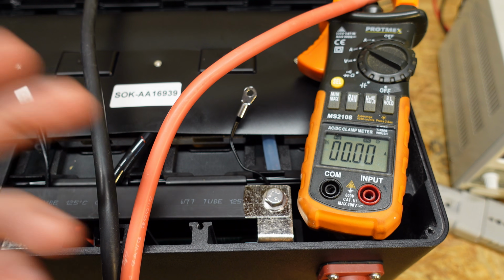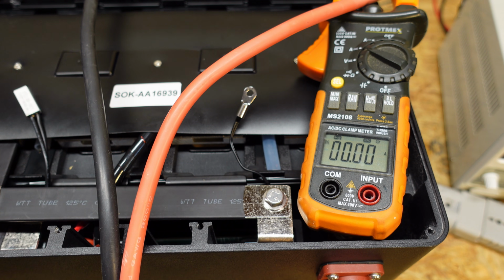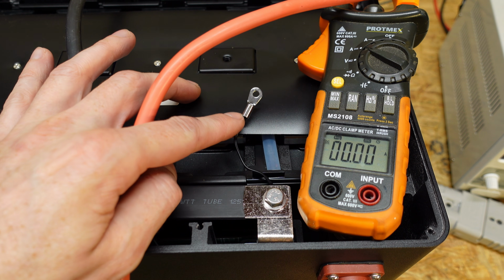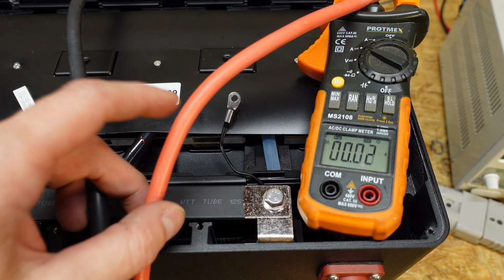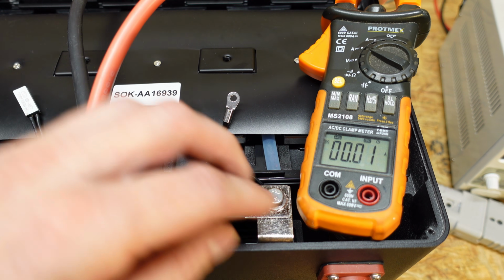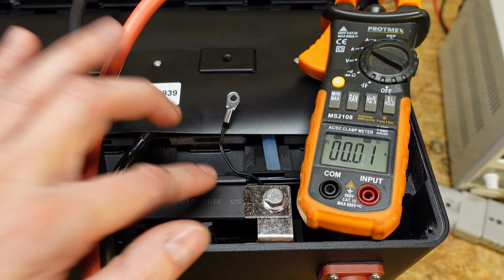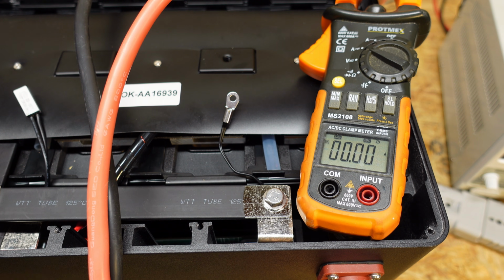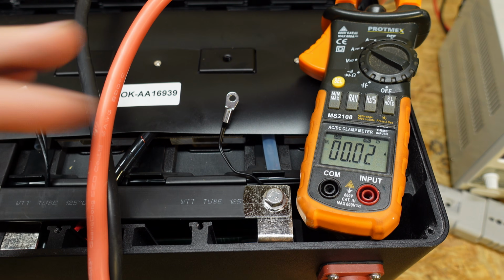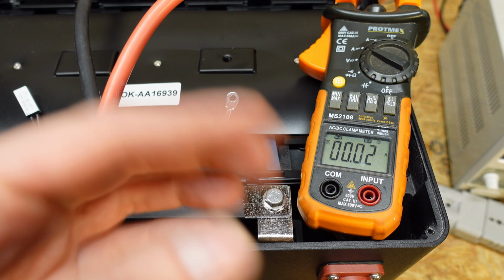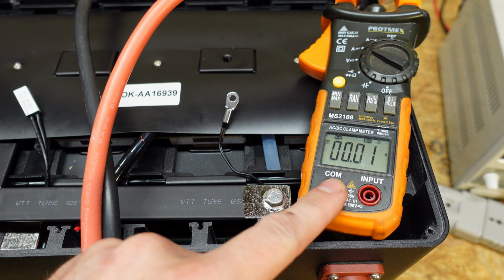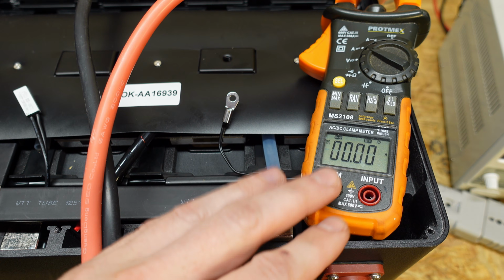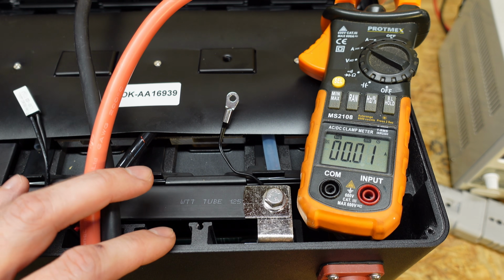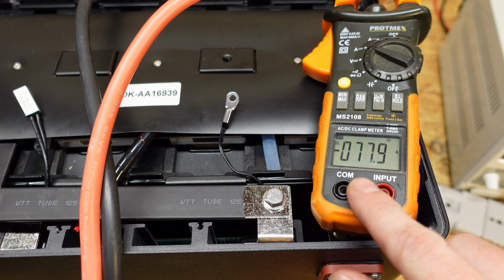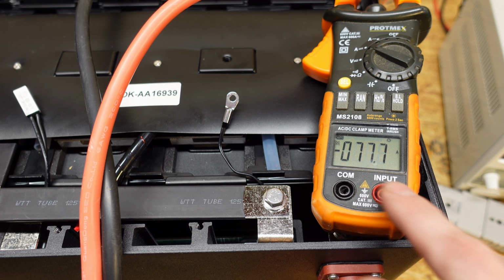Now we're going to test the low temp charge protection and the heater functionality. We have the temperature sensor, or thermistor, and I've got a clamp meter on the positive lead. I'm going to turn on the charger, then spray this temperature sensor with some computer duster, which should drop it well below freezing, and we should see that heater circuit engage. I'm expecting the charge current to drop to about 7 to 8 amps, indicating it's now powering the heater instead of charging the battery. We're charging at approximately 77 to 78 amps.